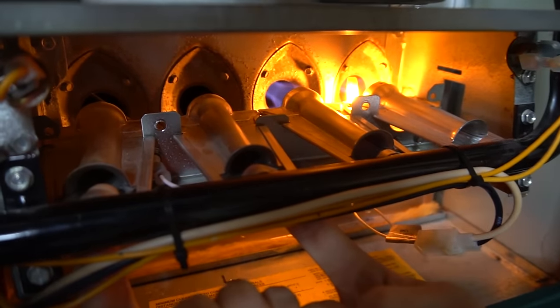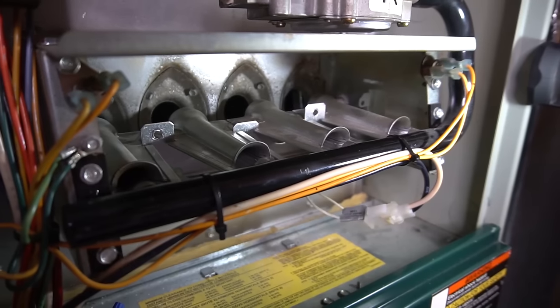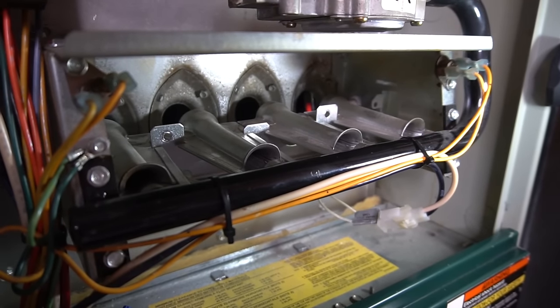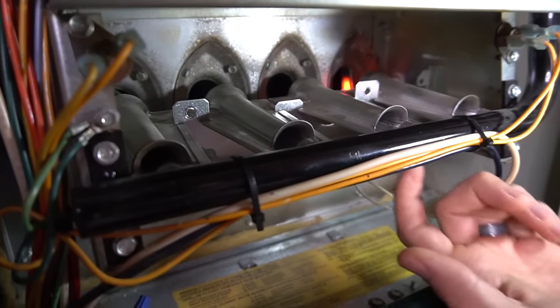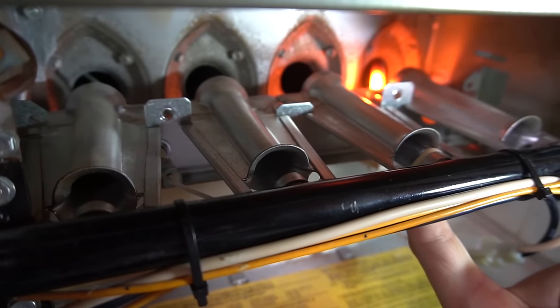So let's wait for this thing to light. So as you can see, only the first two lit, and the next two are plugged. So that was two orifices plugged, and let's simulate just one orifice plugged. Let's plug this one, for example. See what happens.